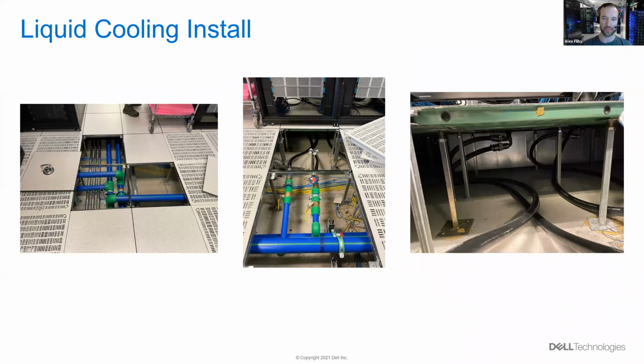I've got a couple more photos from the install. The system doesn't have the chilled water from the facility go straight into the back of the system - there's actually 2 separate loops. The chilled water from the facility goes into the back of the heat exchanger for the CDU, the cooling distribution unit, and that cools down the glycol solution that's actually flowing between all the systems. That glycol secondary loop is the green and blue pipes you see there, and that's what's plumbed to your individual racks. At a rack level, we've got individual valves and flexible hosing, visible in the center and off to the right.